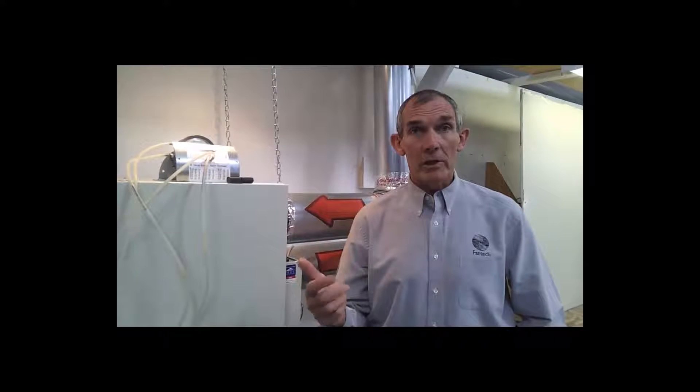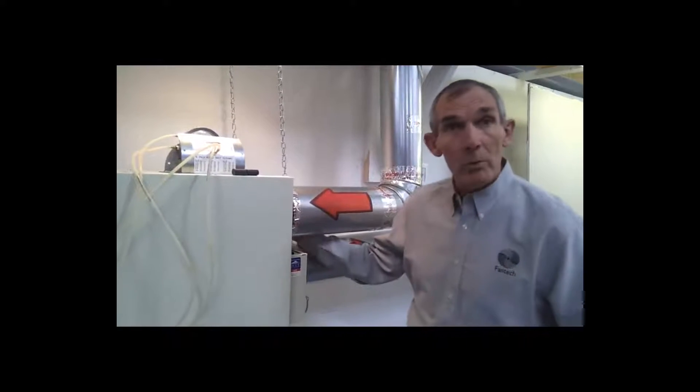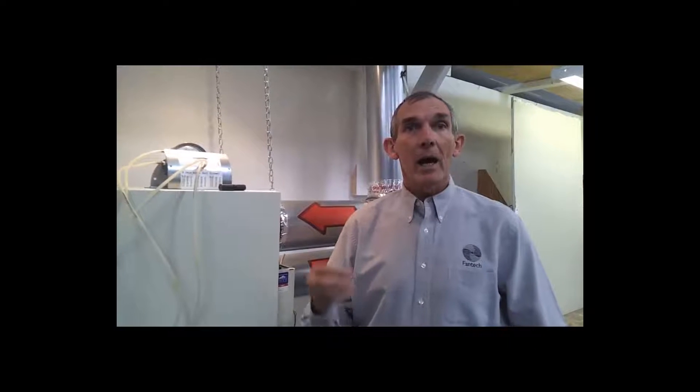Balancing your Fantec heat or energy recovery ventilator. A few points before you start balancing. One, make sure that the unit is not in defrost. Two, prior to balancing turn off all the exhaust fans in the house - that's the kitchen fan, the bathroom fan, the dryer fans. Open the balancing damper on the unit which is integral, and make sure that if it's attached or ducted into a heating or ventilation system, that system is operating on high.